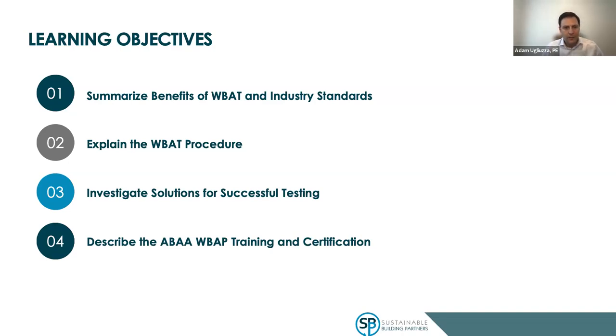And then I'll talk about how we investigate if a building's not passing initially when you're firing up the fans. Don't panic. A lot of the time there are building prep issues or low hanging fruit that you can address and have a successful test. That's not to say don't address all the issues you might find during the test. You should really resolve all of them. But as far as passing the test, depending on what performance criteria you're shooting for, if it's just code level, there are usually pretty easy things you can do to get to a successful test.